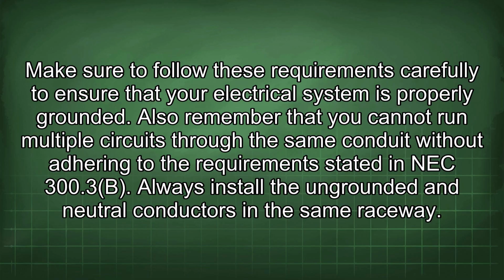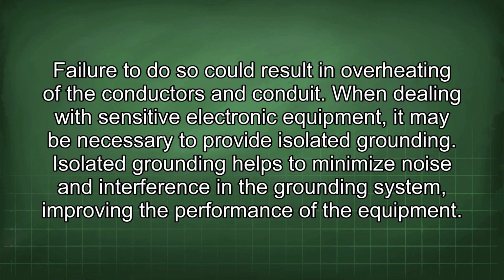Also remember that you cannot run multiple circuits through the same conduit without adhering to the requirements stated in NEC 300.3(B). Always install the ungrounded and neutral conductors in the same raceway. Failure to do so could result in overheating of the conductors and conduit.